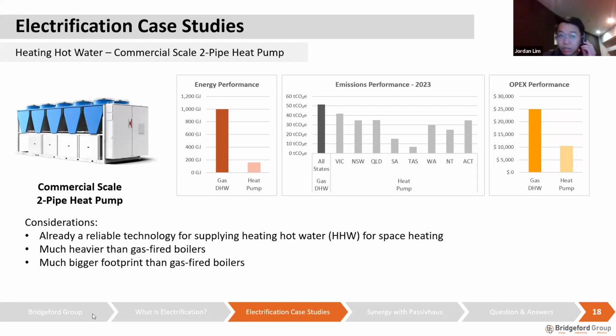The design consideration for this technology is that it's really big. I don't have a scalable figure off the top of my head, but it's not uncommon to see heat pump systems like this be at least about 3 times bigger than a boiler with a similar thermal capacity. So much heavier, much bigger. So the structural integrity of the building does need to be addressed to implement this measure.